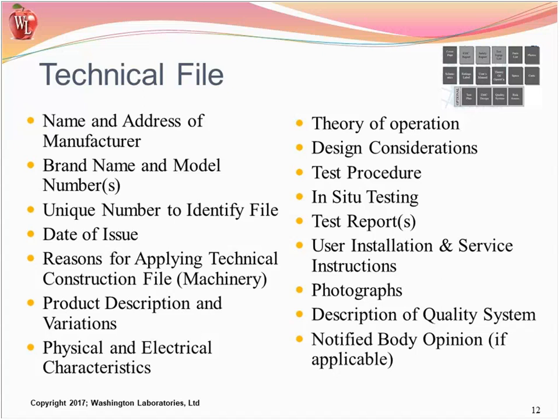This involves making sure your product conforms to the current standard. If there's an update to the European directive or a product standard change, you're declaring conformity to the new one, and any evaluations need to be incorporated. We run into that occasionally where somebody keeps building the same product and fails to account for new rules that suddenly apply, and they didn't update their files.